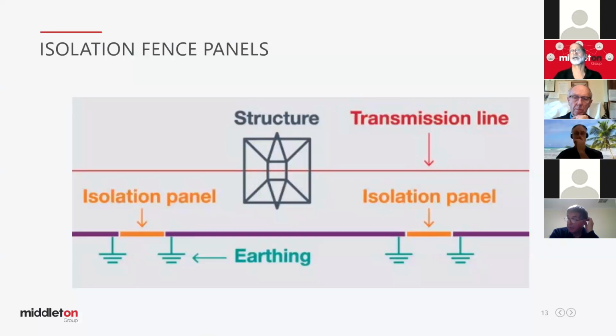If we can introduce auxiliary paths for the fault current, and the fault current doesn't physically go through the earth in the earth grid, it's not going to generate the EPR that generates the touch voltages. So that's a good question and a good solution, David. Thanks for your input.